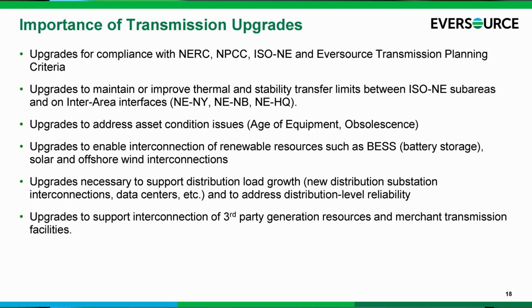Then, as Juan touched upon, the other big driver is the aging existing energy infrastructure. Due to asset condition issues, we keep monitoring the health of assets. We don't replace equipment only because of age, there's usually an issue such as poor condition, a transformer leak, or underground cable insulation leak. There can be environmental or safety issues, or obsolete equipment with no repair parts, and we constantly run an asset condition program to address those asset health issues.